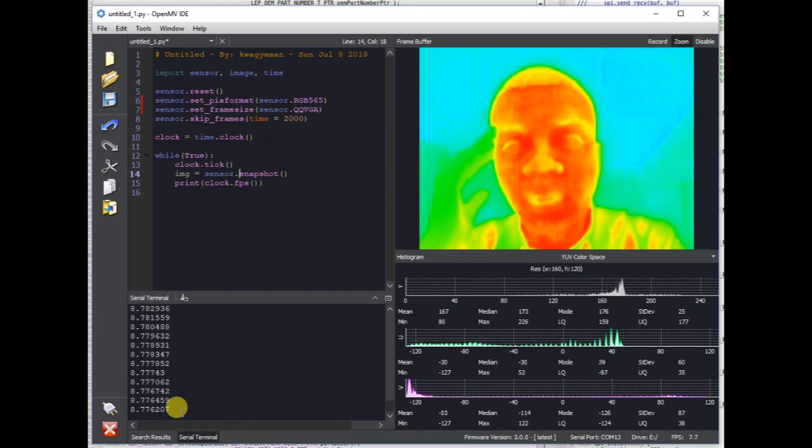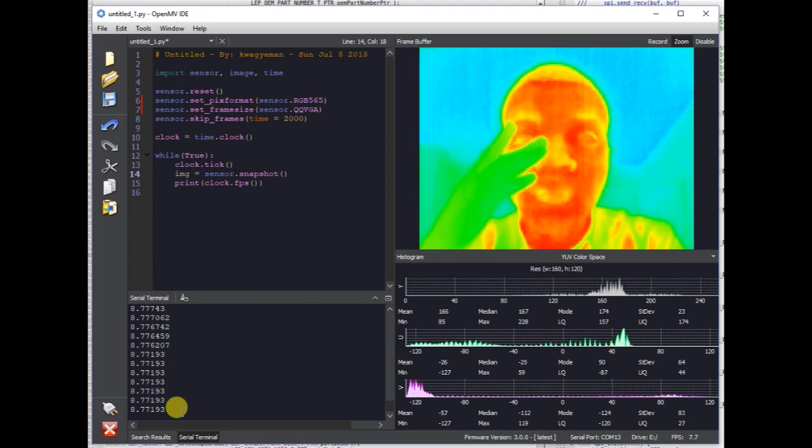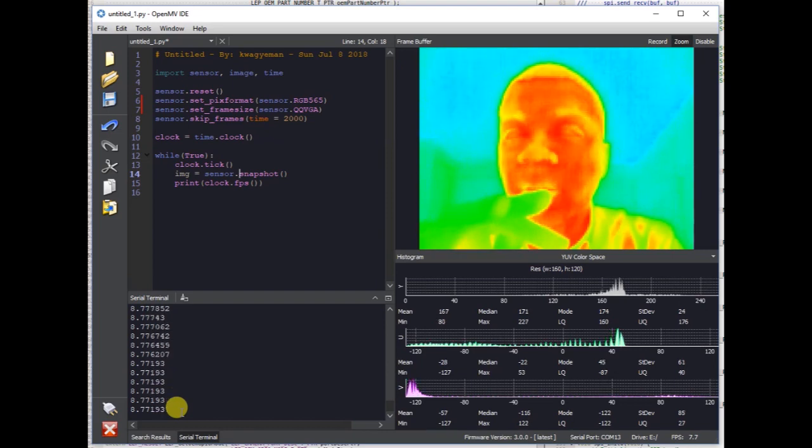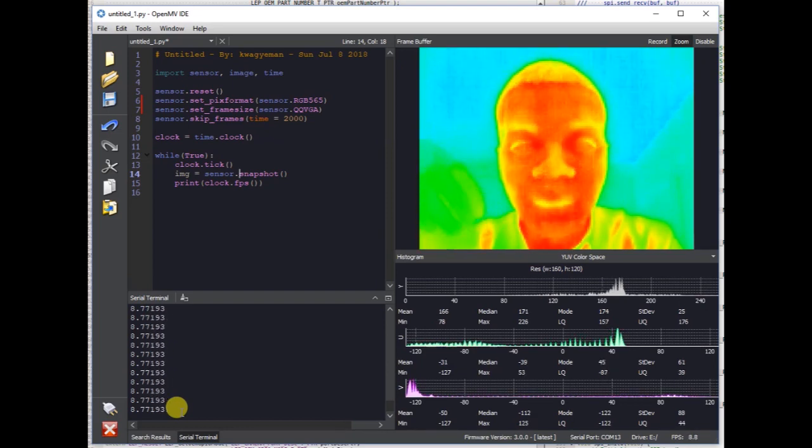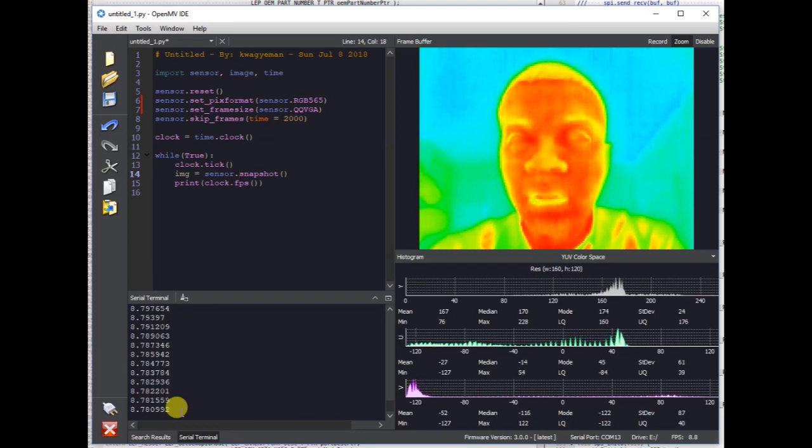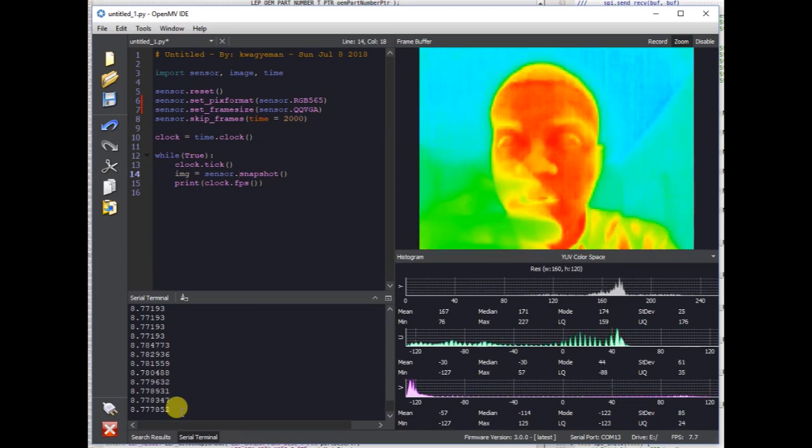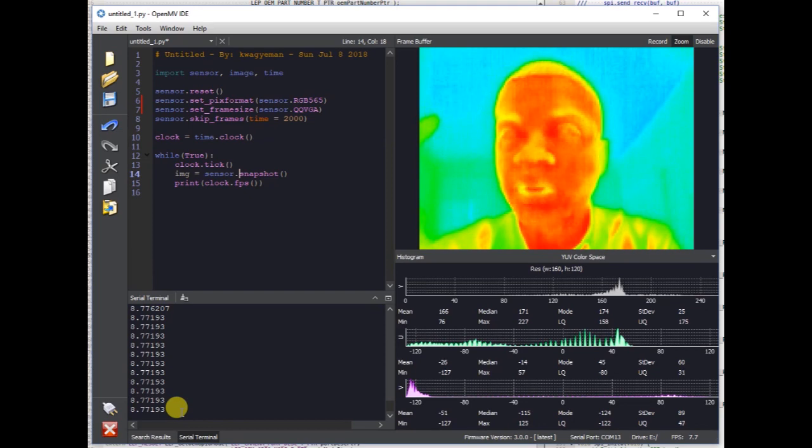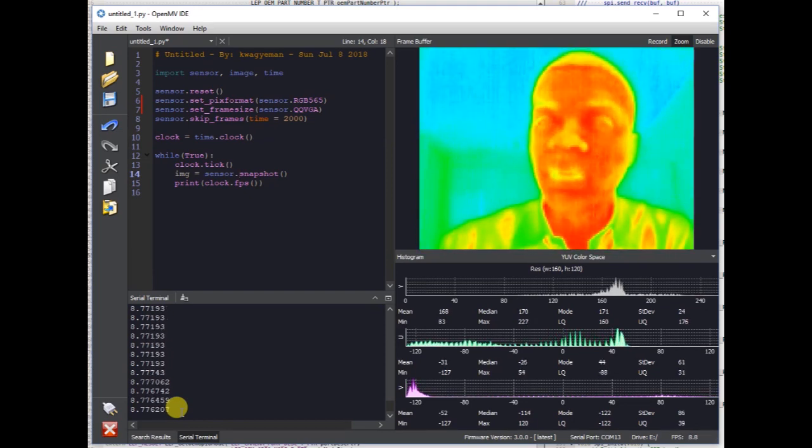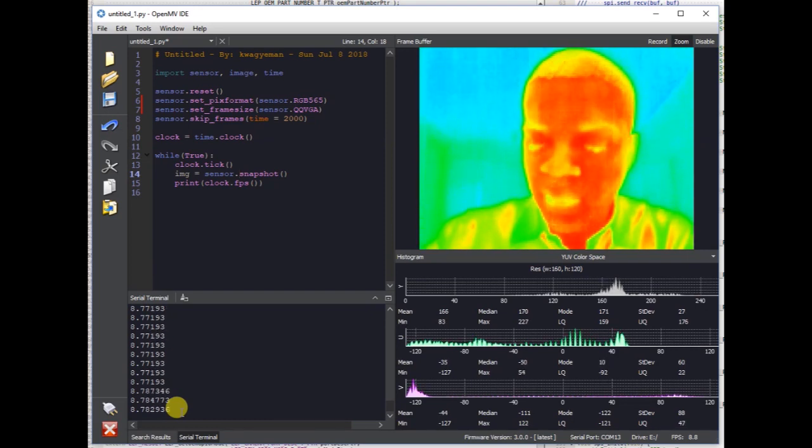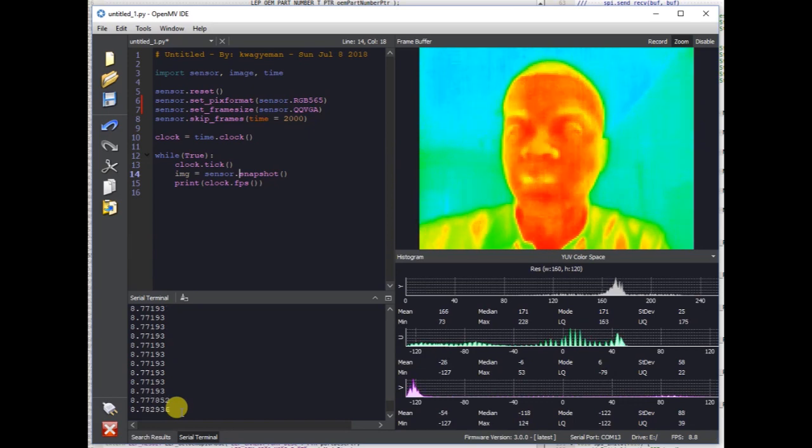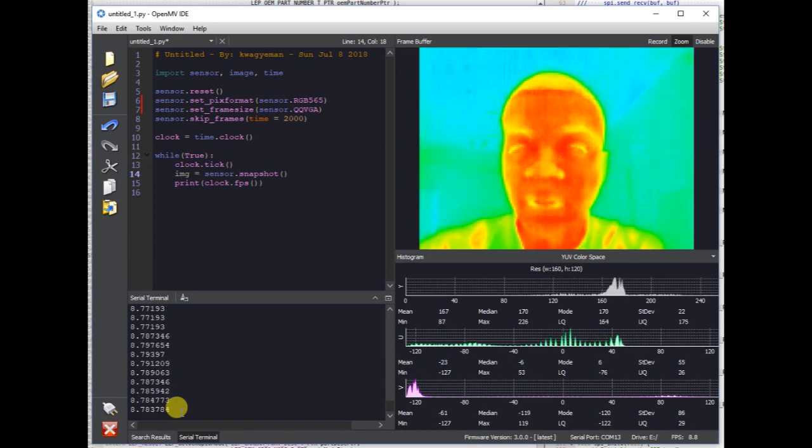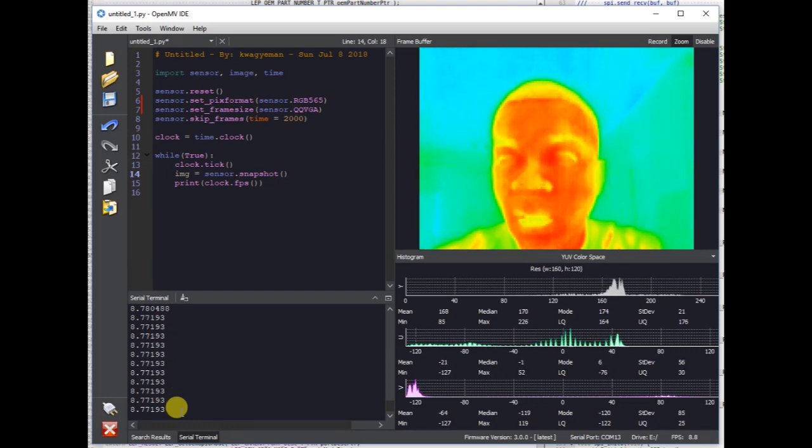So the FLIR Lepton 3 has a shutter on it, which it does flat field correction. Every time you saw that stop where it stopped for about a second, what actually happened was the FLIR Lepton had closed its shutter and corrected. It's doing something called flat field correction where it closes a shutter and it looks at the back of the shutter, which has a solid temperature. And then it's able to figure out how to map a negative image to subtract from the actual image data stream to remove any variances in the image output.